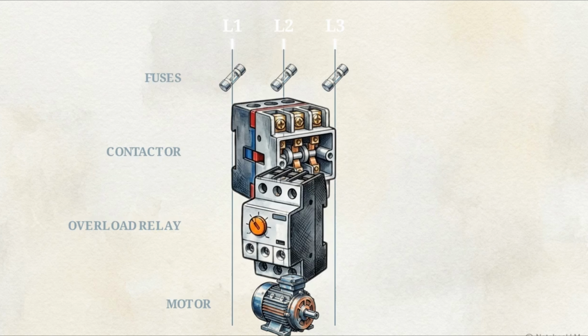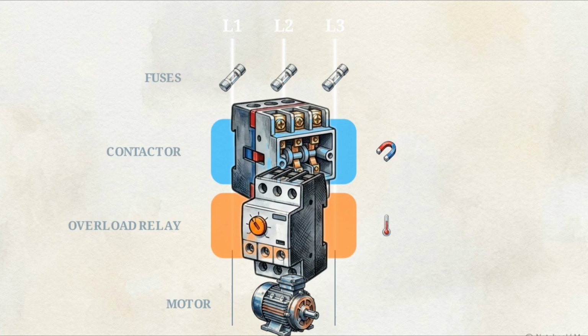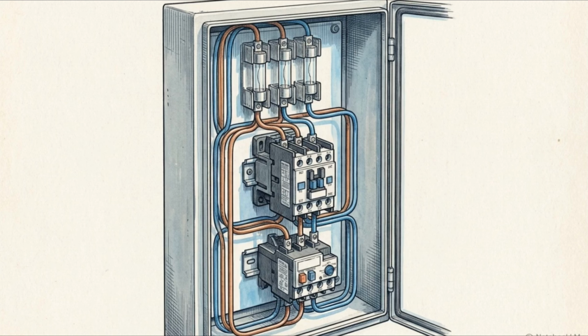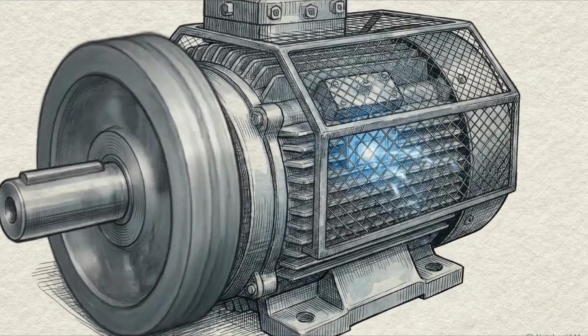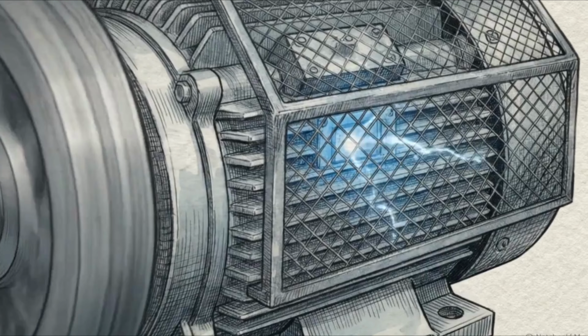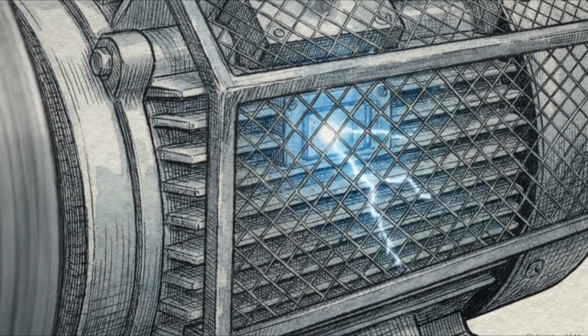Looking at the entire wiring diagram from top to bottom, we can see the exact logic of the complete system. Three-phase power enters from the top, delivering consistent energy. The flow hits the fuses, blocking instantaneous spikes. Electricity then reaches the contactor, halting until it receives a magnetic command. Finally, it passes through the overload relay, ensuring a physical jam doesn't overload the motor. This sequence is a rigid architecture dictated by the physics of power distribution and thermal dynamics. Reading an industrial wiring diagram is ultimately an exercise in recognizing this multi-layered system designed to safely cage and direct extreme raw power.